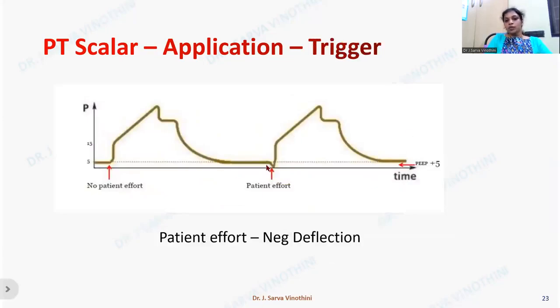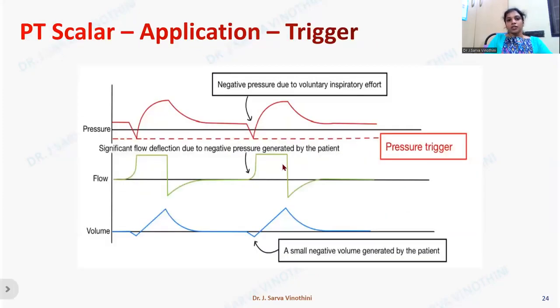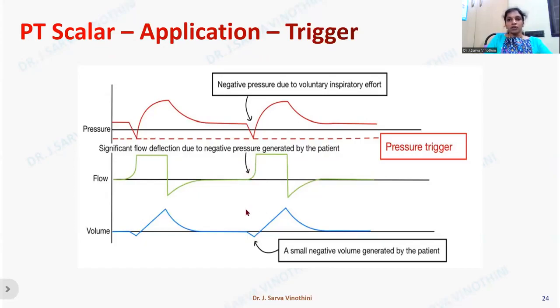The patient's effort can also be seen as a negative deflection in the pressure-time scalar — below the baseline or below the PEEP line. The pressure-time scalar can therefore be used to determine triggering. When the patient's effort reaches the set threshold, an assisted breath is triggered. You can see the negative pressure deflection occurring simultaneously in the flow waveform and volume waveform when an assisted breath is triggered.